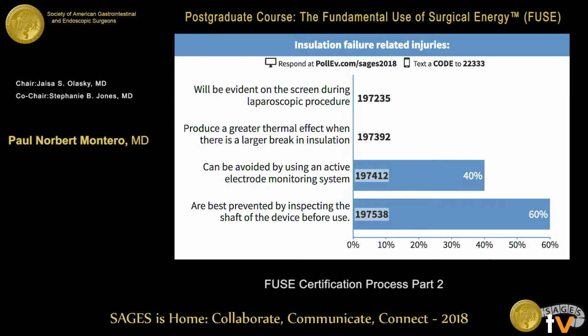So most hospitals have an electronic device that is used to check all of the insulation between all of the cases. But as Pascal says, it's not 100%. Most of the injuries, though, we see are capacitive coupling injuries and not insulation failure injuries, so that when you're doing a lap chole and you touch the side of the instrument, say the cautery, to the liver, and you see a little burn along the liver, that's a capacitive coupling injury.